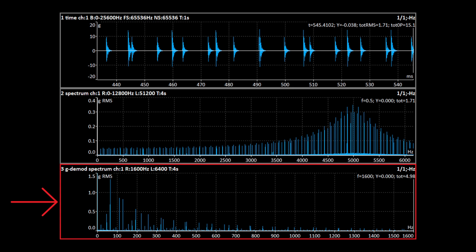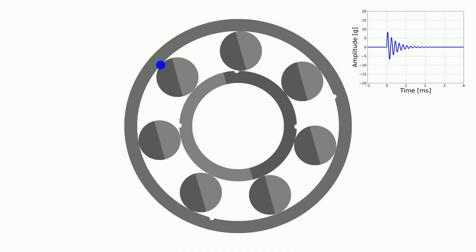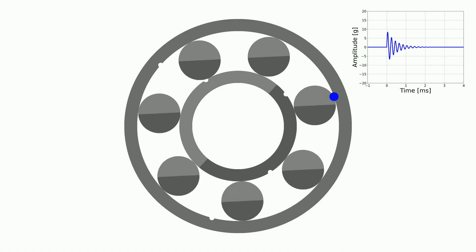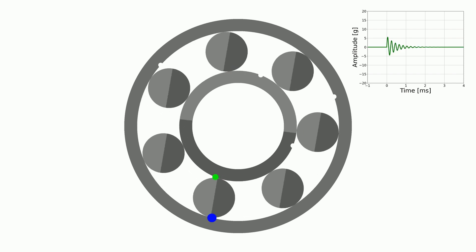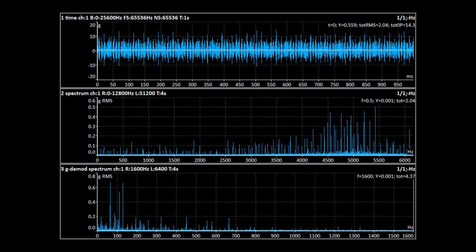The demodulated spectrum shows both frequencies and harmonics of the BPFO and the BPFI. We would see something similar if the number of faults on both races was greater. It does not matter how many faults are there. They repeat. Therefore, we see the important frequencies in the demodulated spectrum.